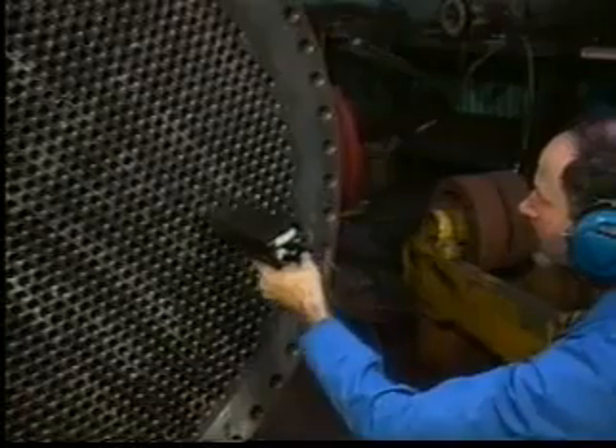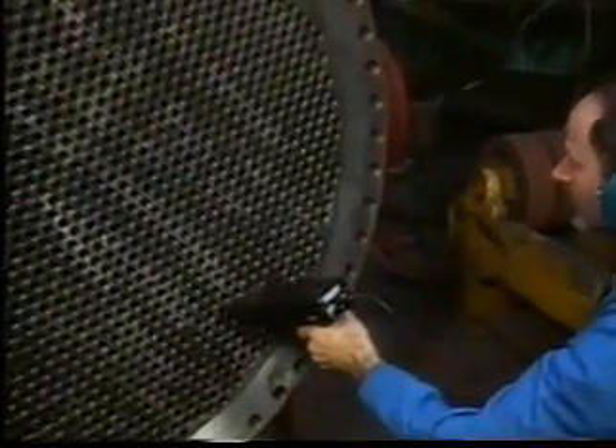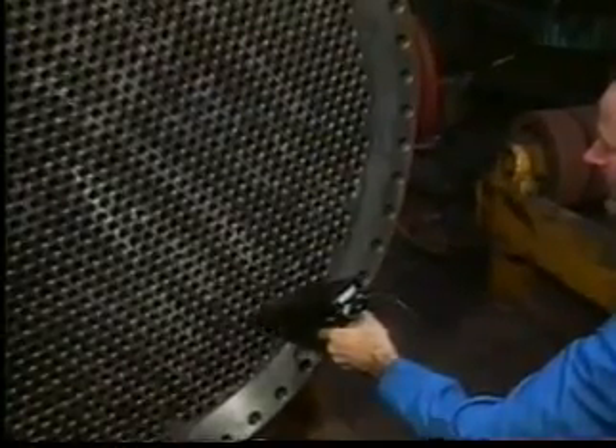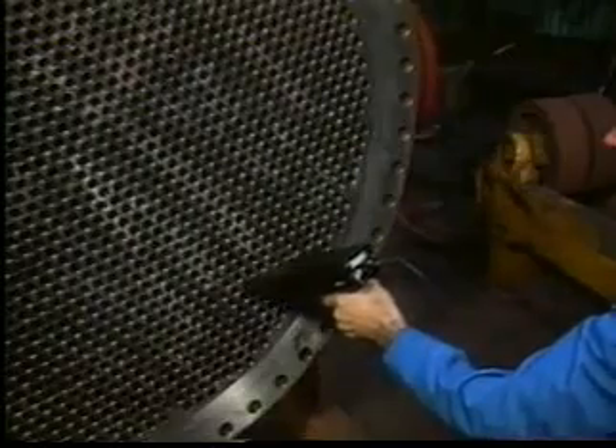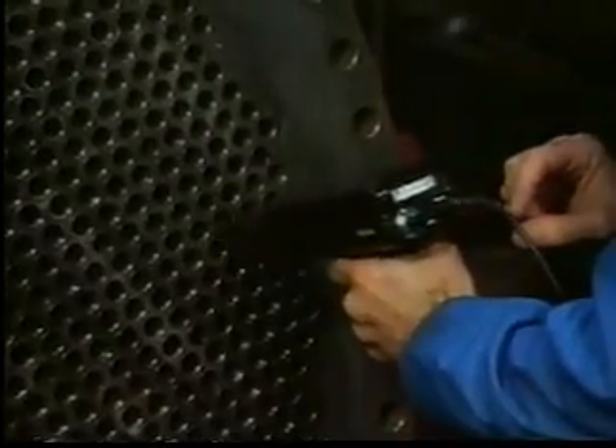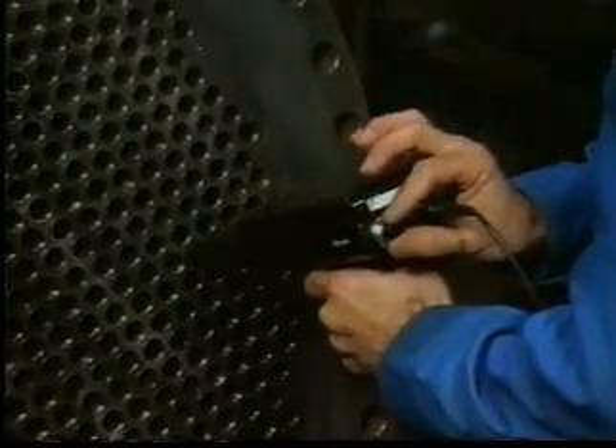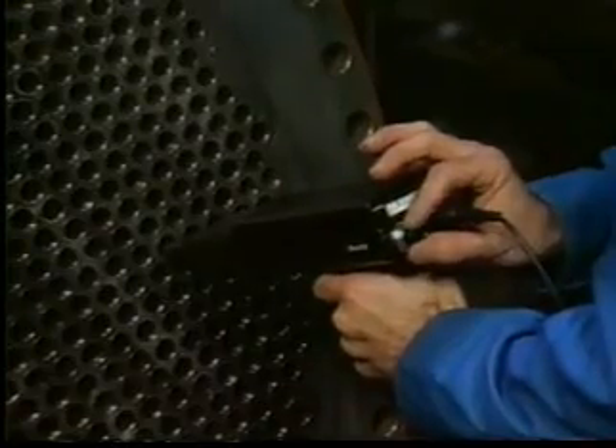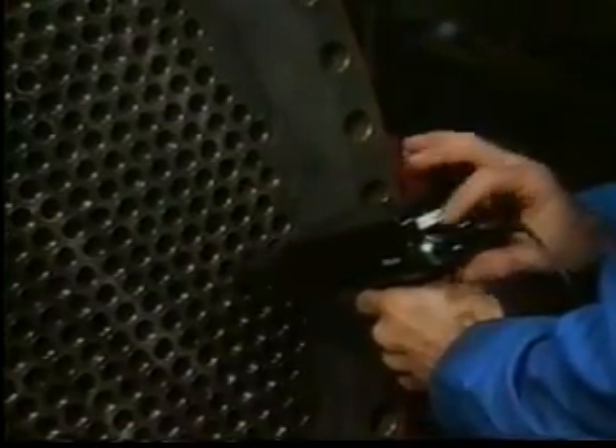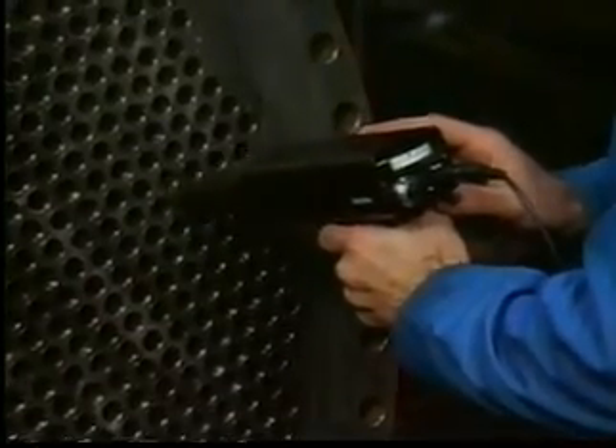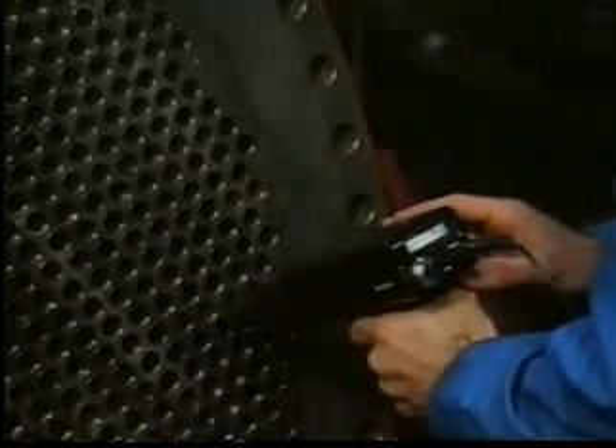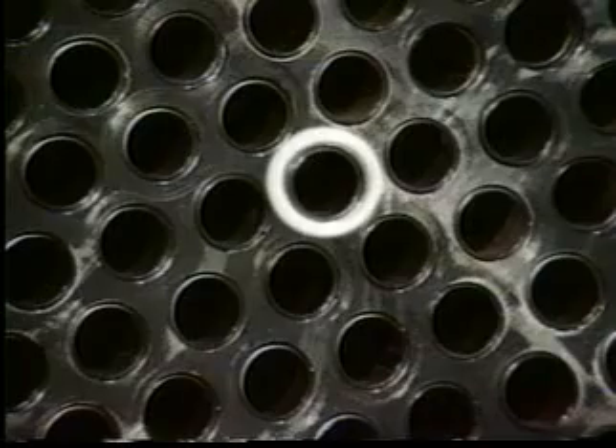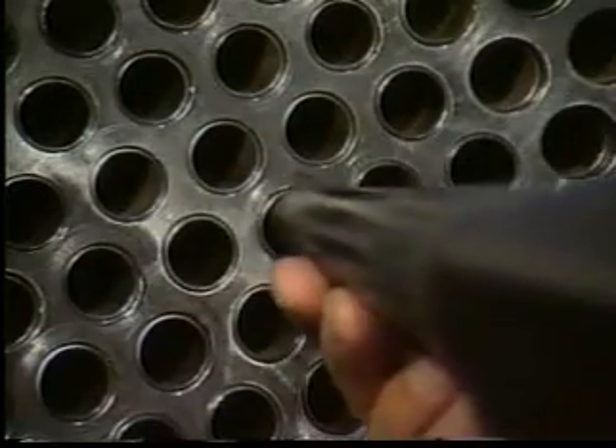As we move away from these areas, sound intensities will change, producing new zones. When you see a change in intensity levels and recognize there is a new area, readjust the sensitivity to read 50 on the meter again and continue testing until you enter another zone. For central areas, bring the ultraprobe sensitivity back up to normal. You may also increase the amplitude of the tone generator as the distance away from the vibration area increases. Use this method to check the integrity of the tube roll. Grossly thin spots along the tube will vibrate and therefore may also be recognized.